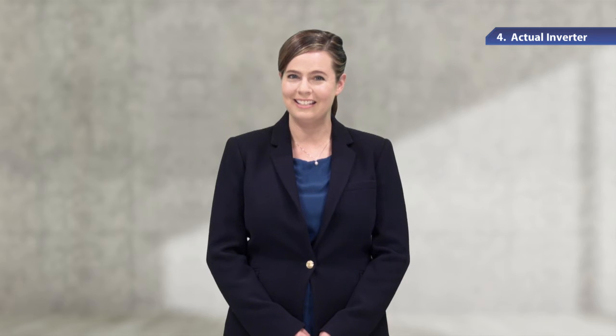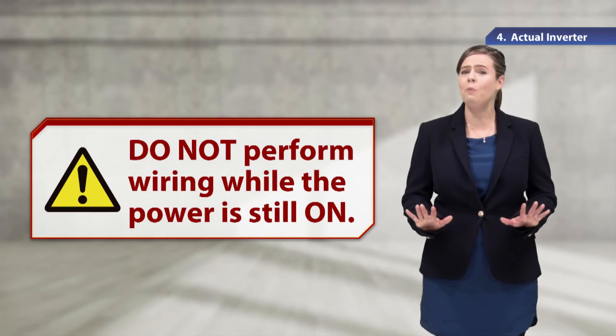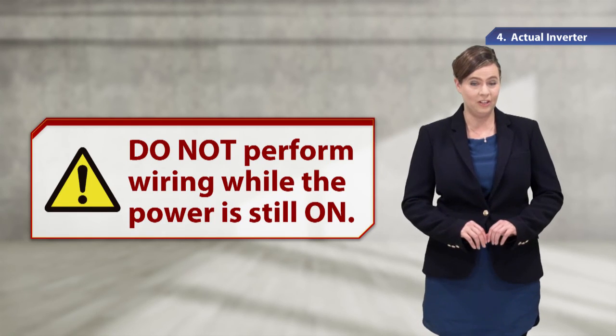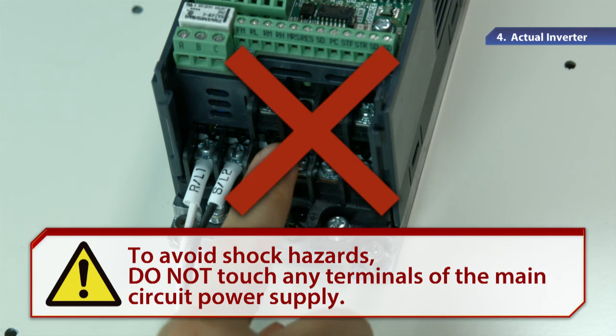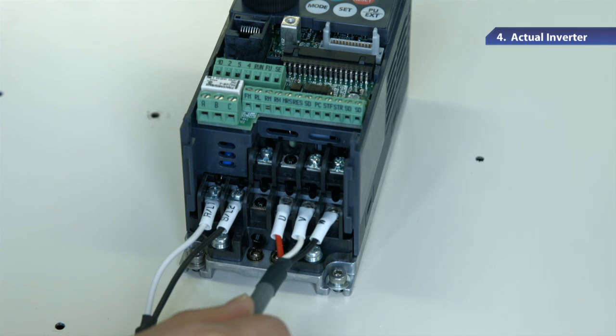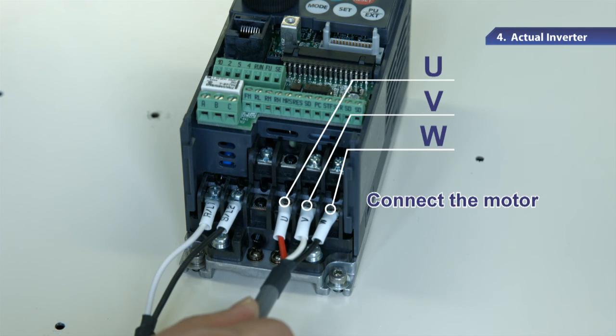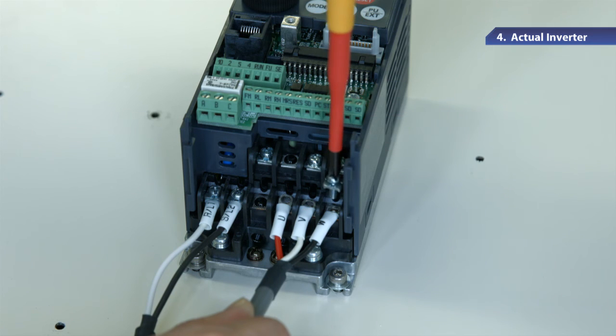Let's connect the motor next. Do not attempt any wiring work while the power is still on. To avoid shock hazards, do not touch any terminals of the main circuit power supply. Use the main circuit terminals U, V, and W of the inverter to connect the motor.